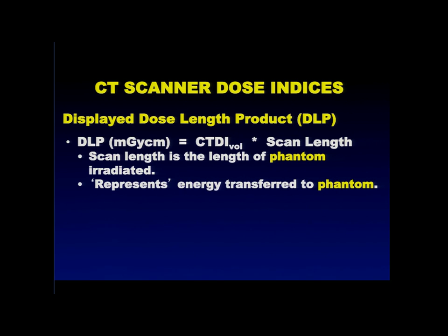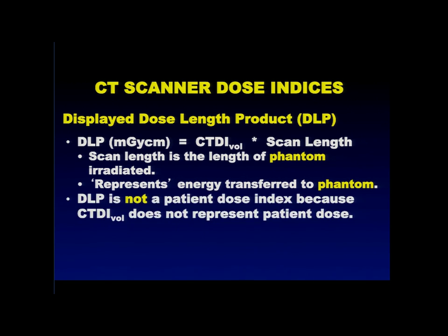So what does it represent? Well, it represents the energy that's transferred to the phantom, not to the patient. So DLP is not a patient dose index because CTDI vol isn't. So why do we use CTDI vol and DLP as an indicator of patient dose? Well, for about 30 years, it was all we had.